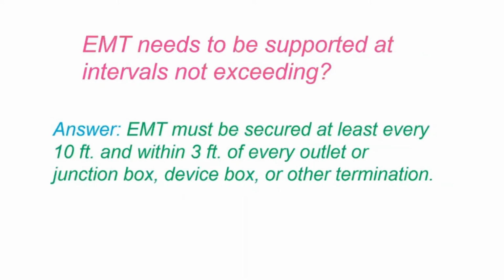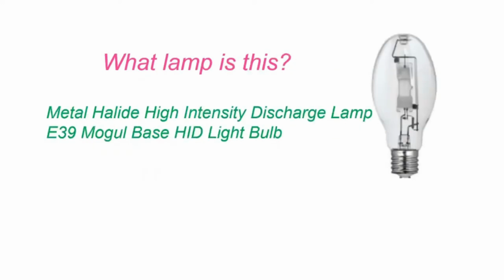EMT, or electrical metallic tubing, needs to be supported at intervals not exceeding what? EMT must be secured at least every 10 feet and within 3 feet of every outlet box, junction box, device box, or other termination. What lamp is this? Metal halide high intensity discharge lamp, E39 Mogul base.